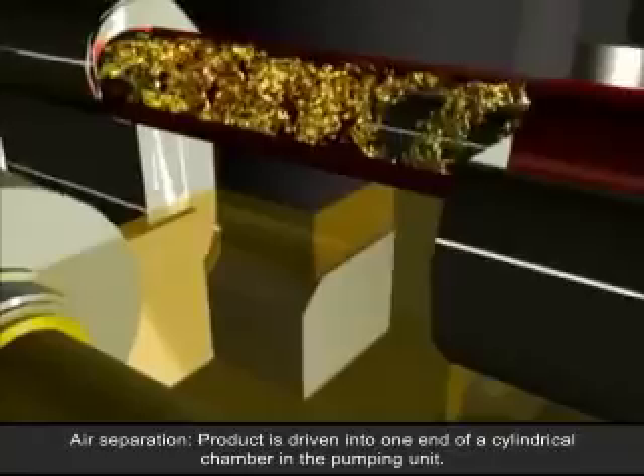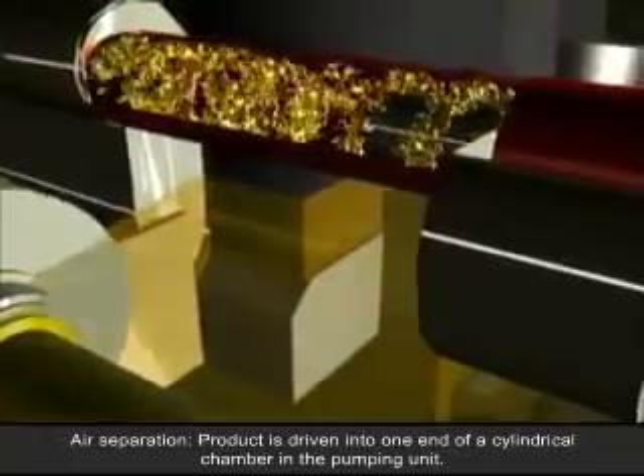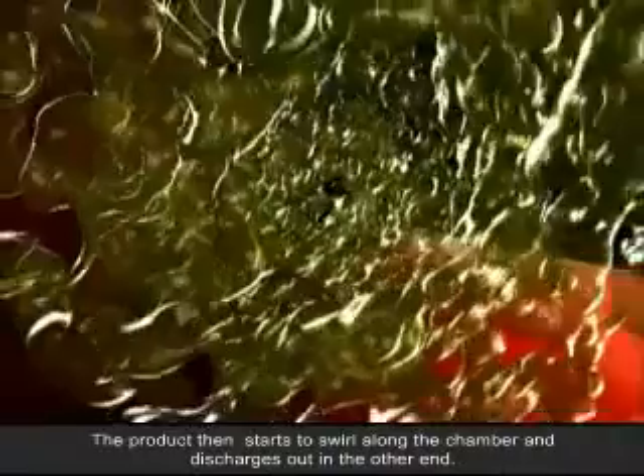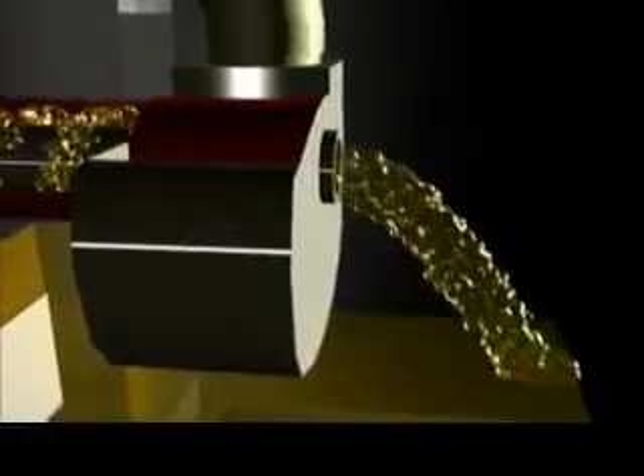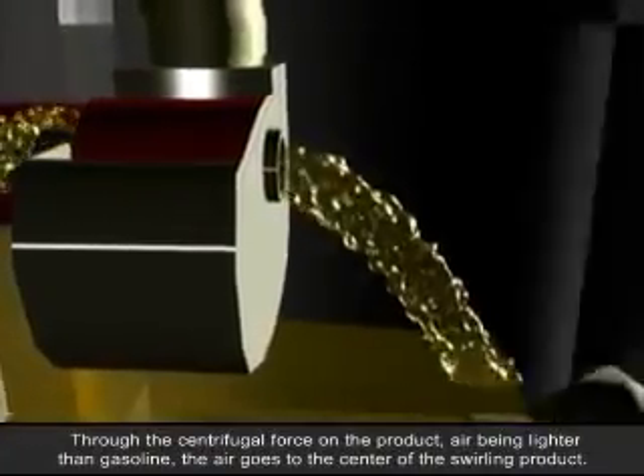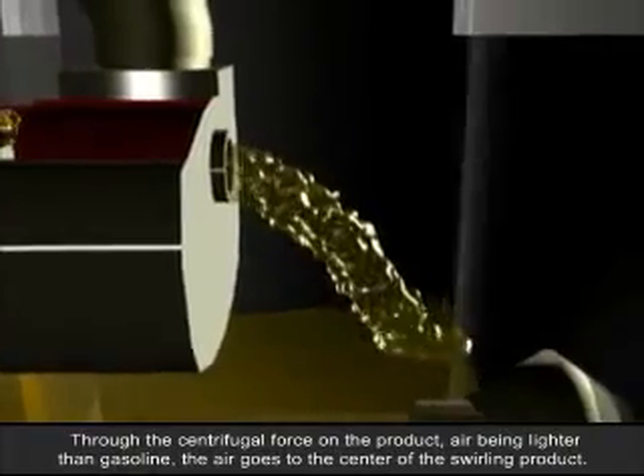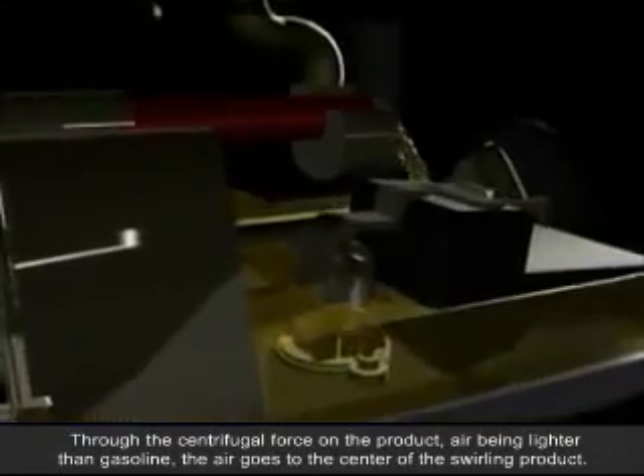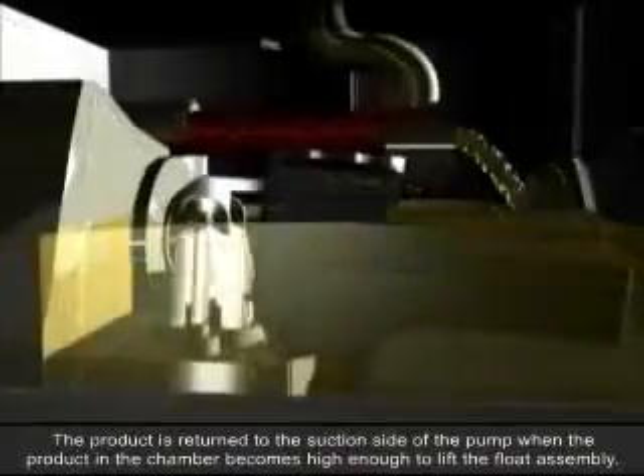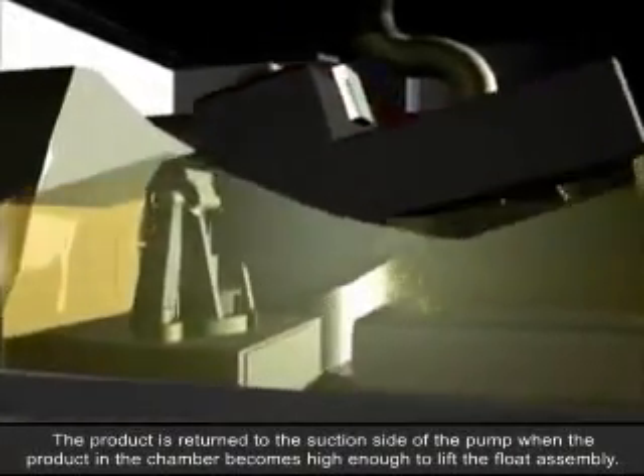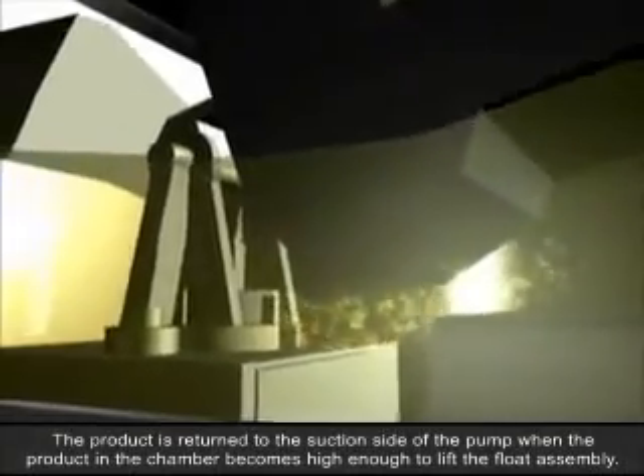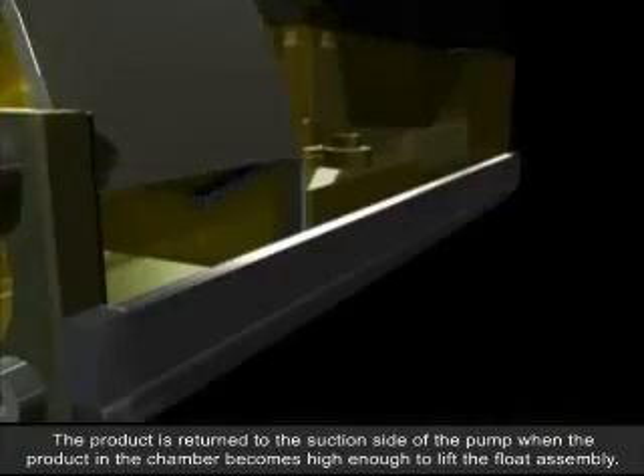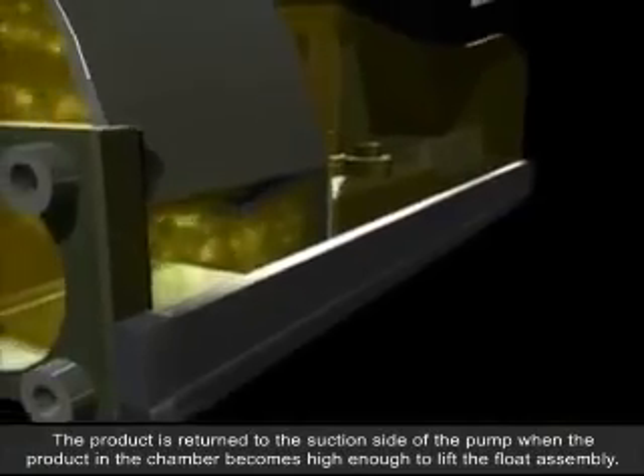Air separation. Product is driven into one end of a cylindrical chamber in the pumping unit. The product then starts to swirl along the chamber and discharges out the other end. Through the centrifugal force on the product, air being lighter than gasoline, the air goes to the center of the swirling product. The product is returned to the suction side of the pump when the product in the chamber becomes high enough to lift the float assembly.